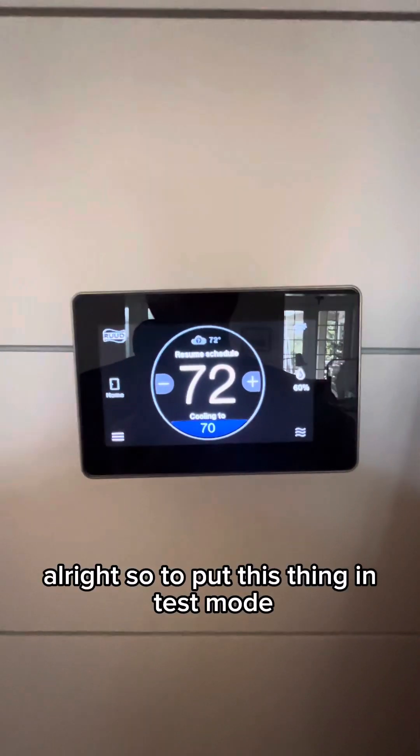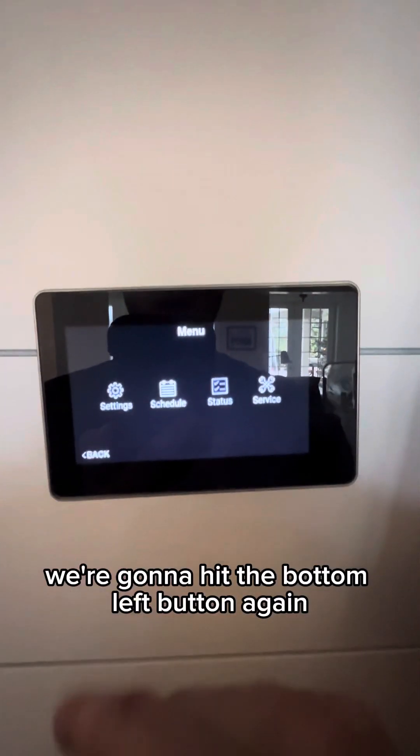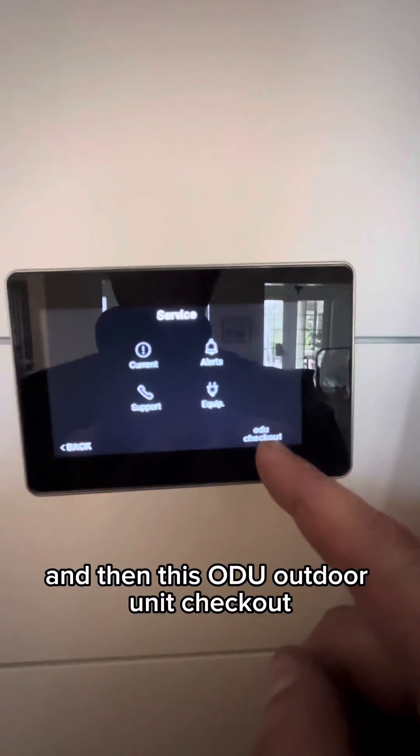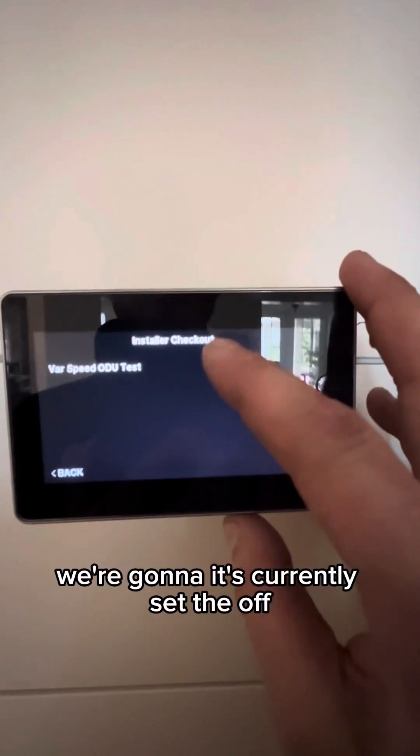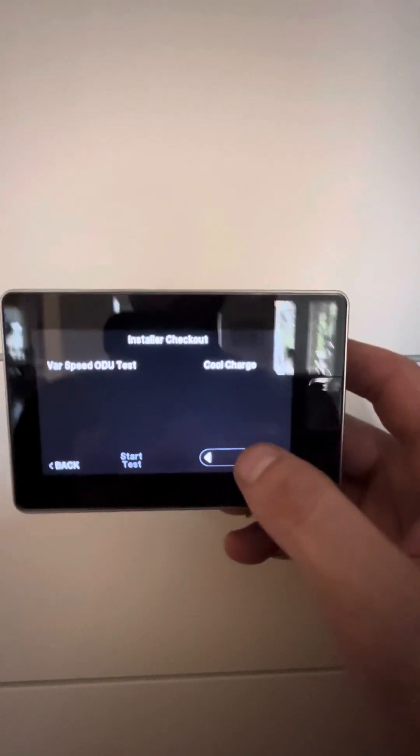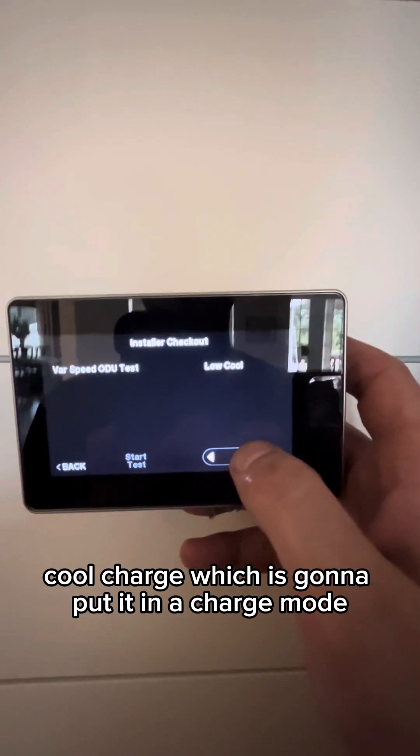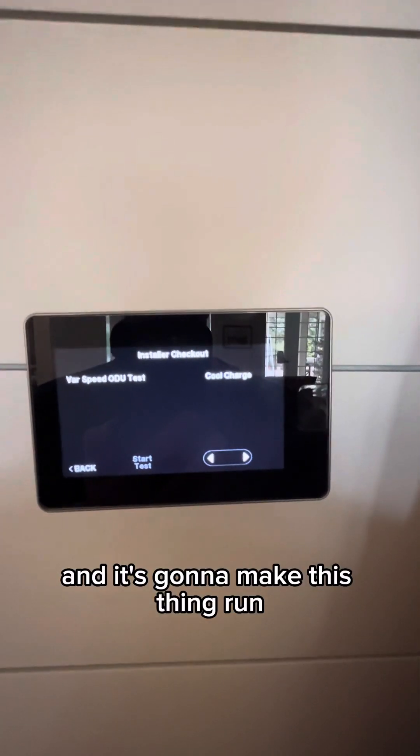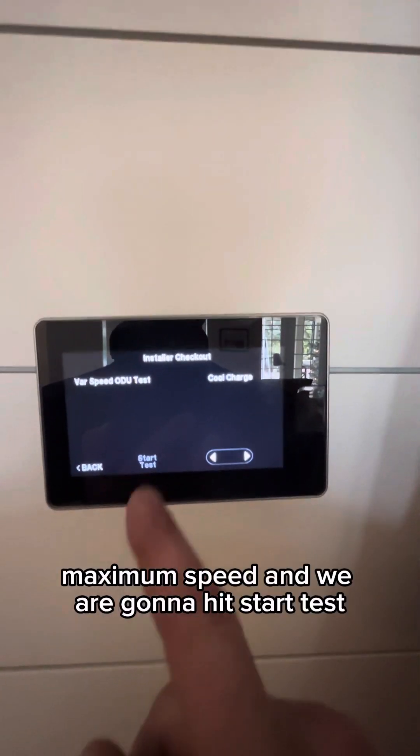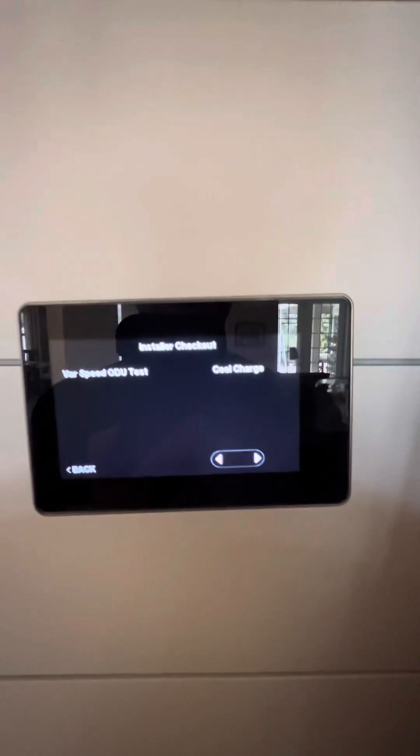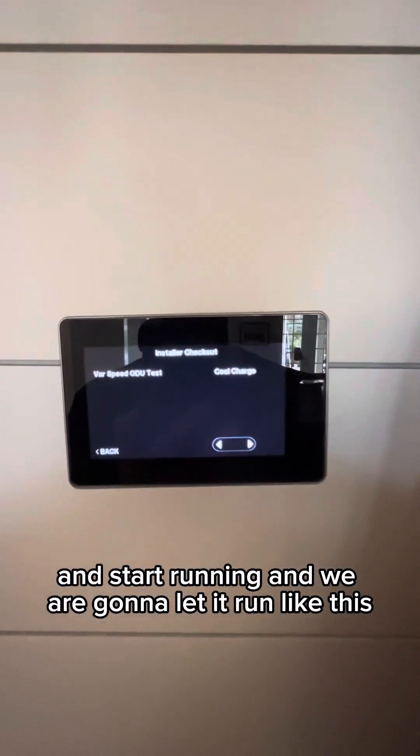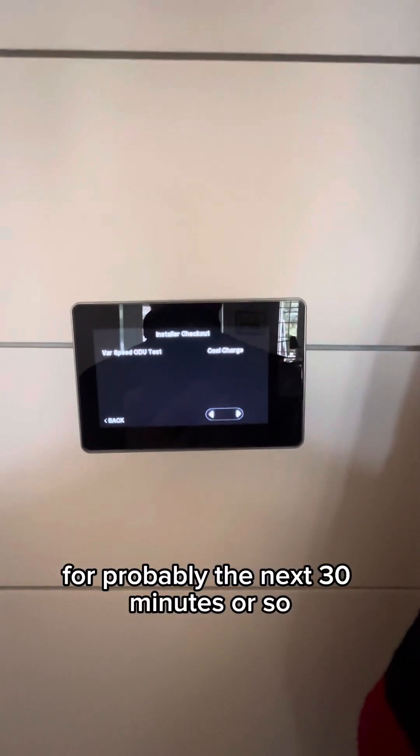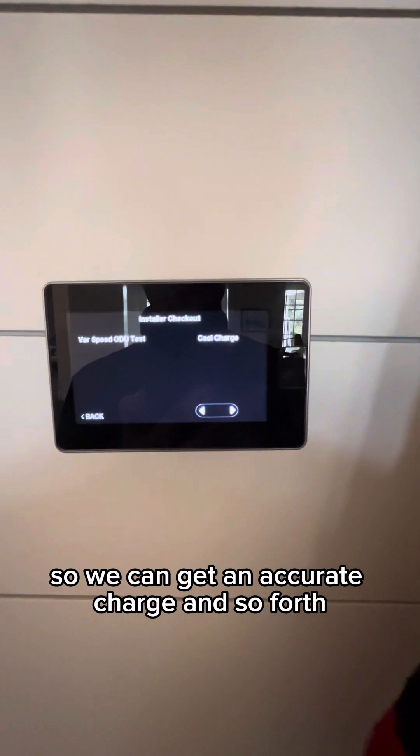All right. So to put this thing in test mode, we're going to hit the bottom left button. We're going to click service. And then this ODU outdoor unit checkout. It's currently set to off. What we're going to do is turn it to cool charge, which is going to put it in a charge mode and it's going to make this thing run at maximum efficiency, maximum speed. And we are going to hit start test. This system will turn on and start running. And we are going to let it run like this for probably the next 30 minutes or so so we can get an accurate charge and so forth.